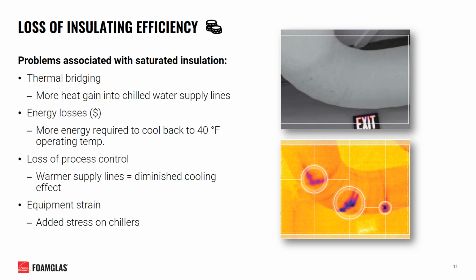This also leads to a loss of process control. Warmer supply lines will lead to a diminished cooling effect in the commercial building as a whole. And this also puts extra strain on your equipment, putting added stress on the chillers in order to reduce the temperature of that chilled water back down to the operating temp it needed to be at.